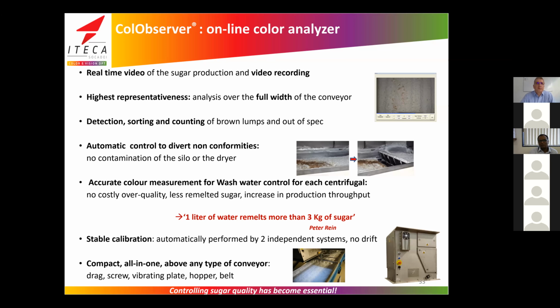No, in fact our system is complete. We provide our system with a PLC embedded inside and with a computer located in the control room. And after that, we have a connection between our system and the plant system, so we usually use Profibus, Profinet, Modbus TCP, and so on.